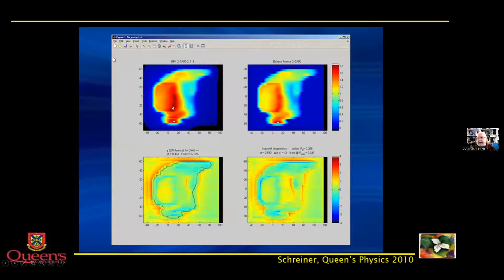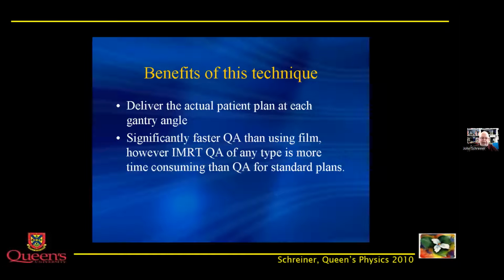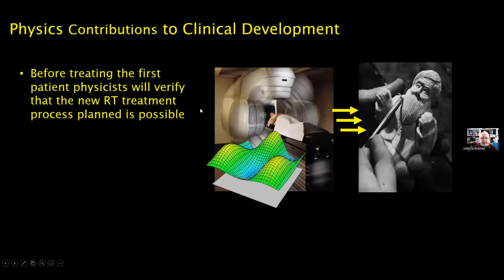So one of the steps in our clinic is to validate that the control parameters have gone to the machine appropriately by looking at the fluence patterns. And there's all kinds of metrics that one can use to make sure that that's acceptable. So we actually deliver the actual patient plan at all of the various angles that are going to be delivered, and we make sure that the expected fluences are what they are before the patient gets their first treatment in Kingston. Different centers do that slightly differently. So again, one of the other things that the physicist is involved with.